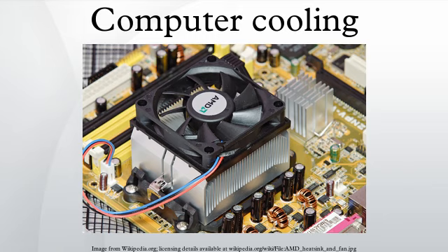Many air and liquid cooling systems were devised and investigated, using methods such as natural and forced convection, direct air impingement, direct liquid immersion and forced convection, pool boiling, falling films, flow boiling, and liquid jet impingement. Mathematical analysis was used to predict temperature rises of components for each possible cooling system geometry. IBM developed 3 generations of the thermal conduction module, which used a water-cooled cold plate in direct thermal contact with integrated circuit packages. Each package had a thermally conductive pin pressed onto it, and helium gas surrounded chips and heat-conducting pins.